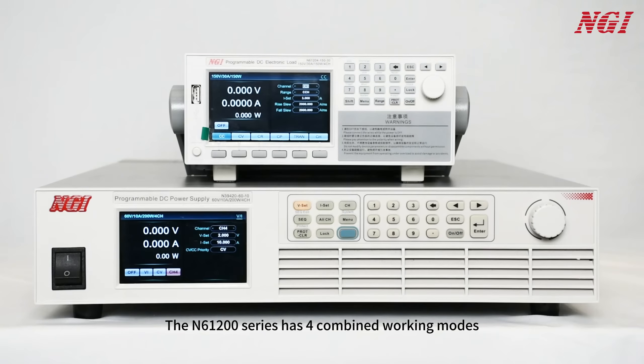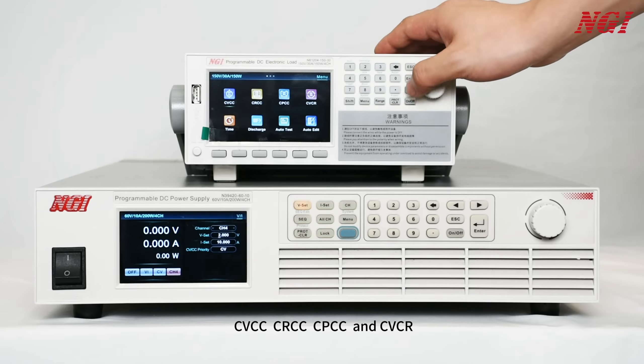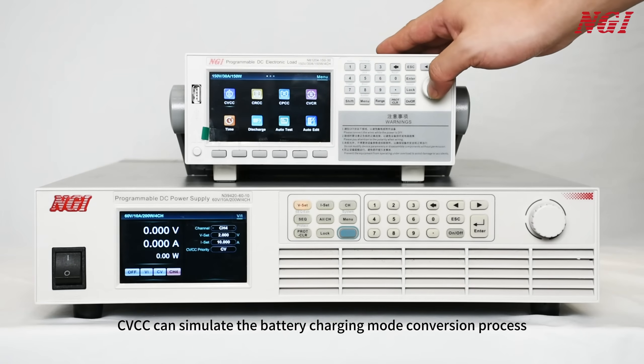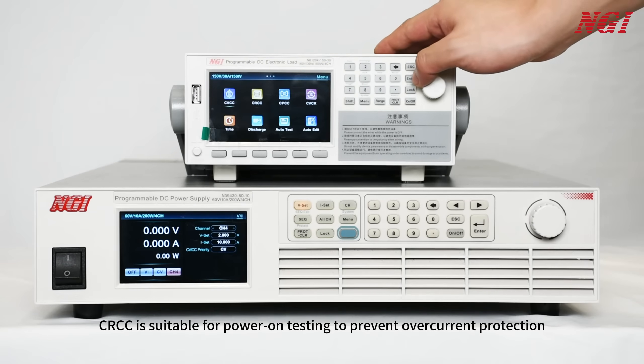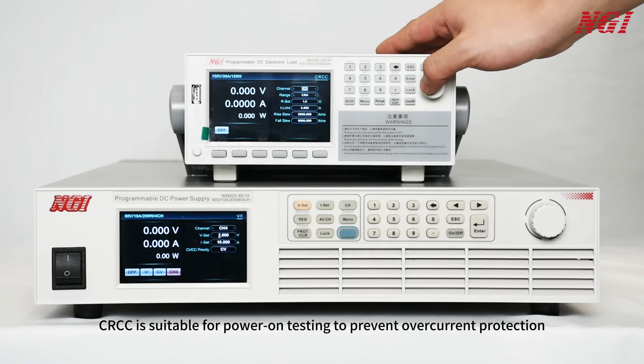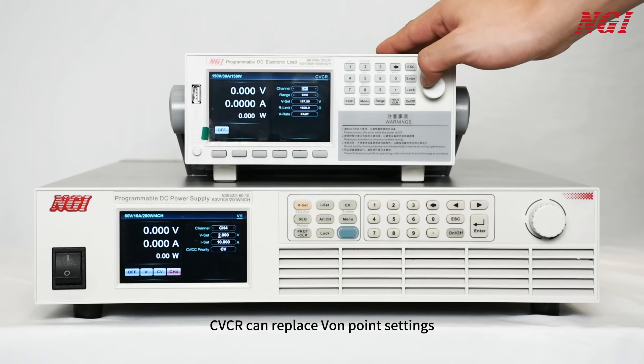The N61200 series has 4 combined working modes: CVCC, CRCC, CPCC, and CVCR. CVCC can simulate the battery charging mode conversion process. CRCC is suitable for power-on testing to prevent overcurrent protection. CVCR can replace Von point settings.